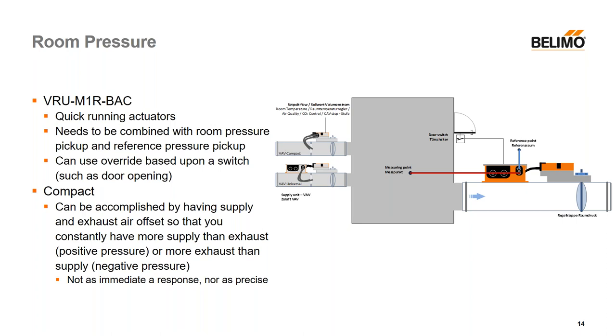There are other ways to do room pressurization using our products. One example is using the compact line — you need both supply and exhaust air controlled using either VAV or CAV, and the idea is that you maintain a constant ratio where either supply is more than exhaust (giving positive pressure) or exhaust is always greater than supply (giving negative pressure). It's not as immediate a response, nor as precise, but it remains an option if you're looking to do something a bit more simply.